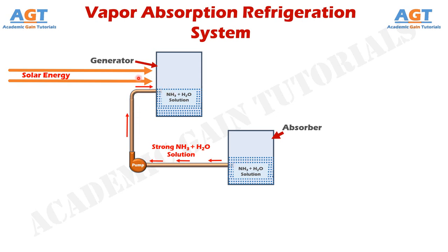Now, when the solution of ammonia and water reaches the generator, heat is produced inside the generator using the solar energy supplied to it. And when heat is applied to this solution, both ammonia and water from this ammonia-water solution turn into vapor inside this generator.